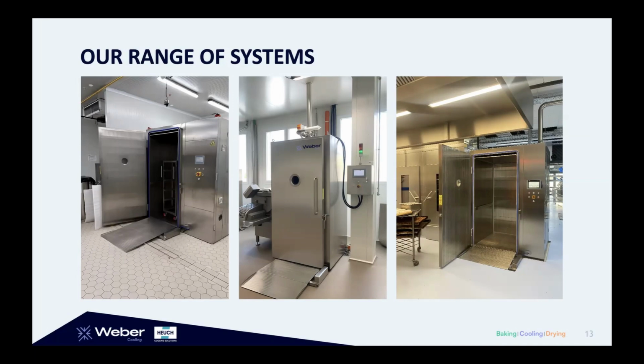So for products that are a bit more liquid, if you vacuum cool a bit slower, it can limit the splashing. We have a PLC where you can insert many different recipes. For cooling food, usually it's more or less straightforward, 20 to 25 minutes, going down to 5 degrees. But you can insert different recipes going down only to 40 degrees or 30, all depending on your process and the end temperature you're looking for.